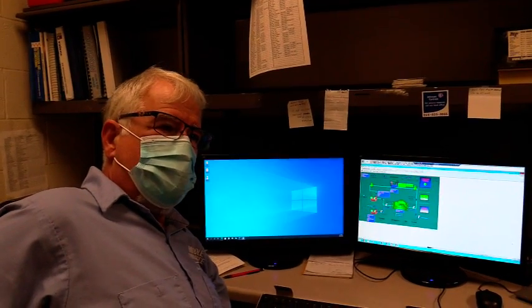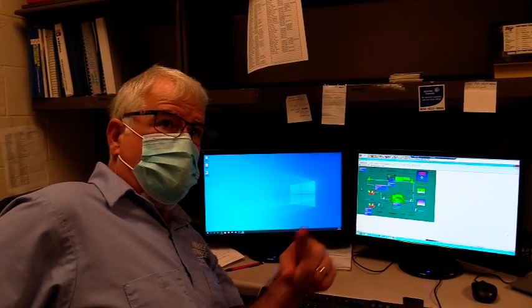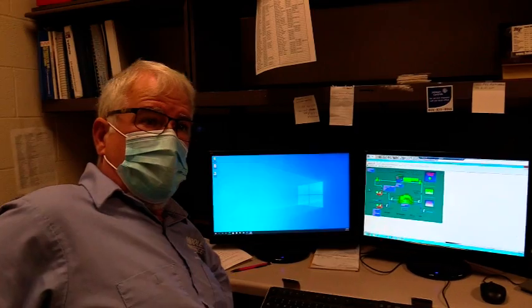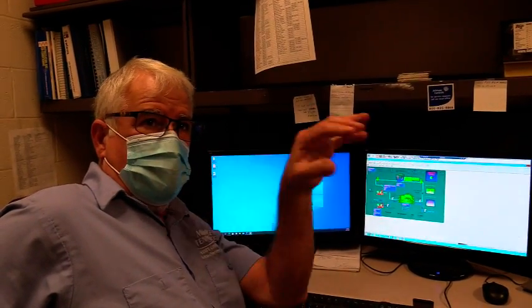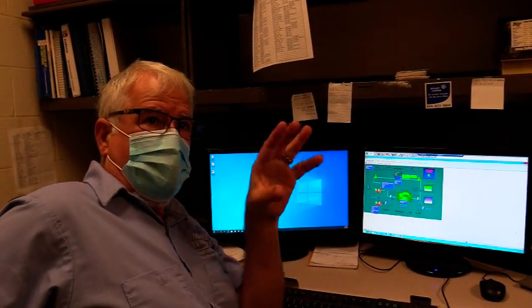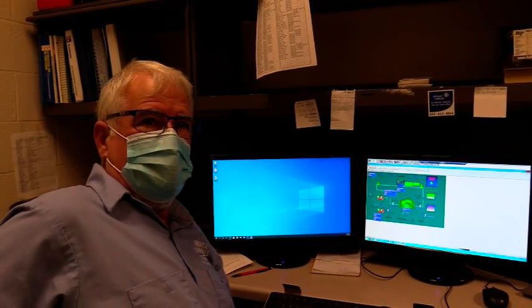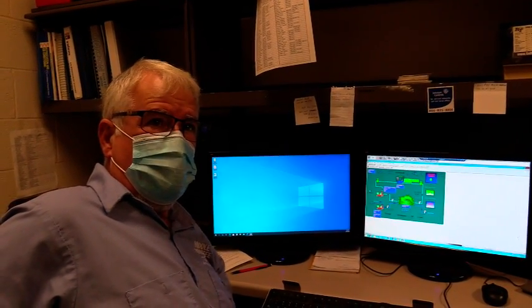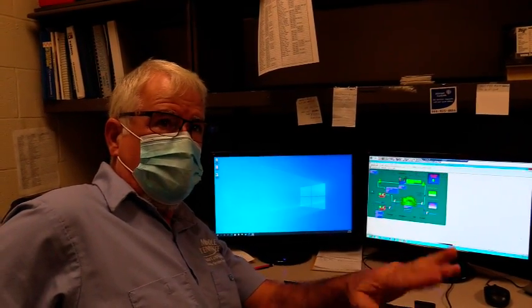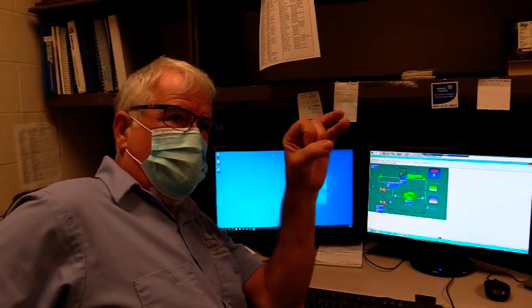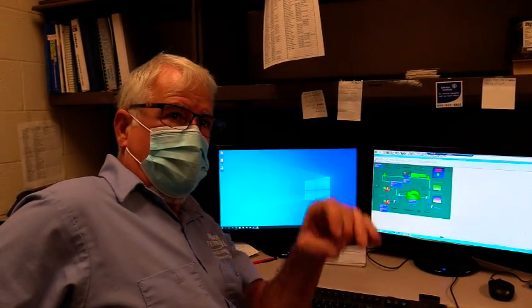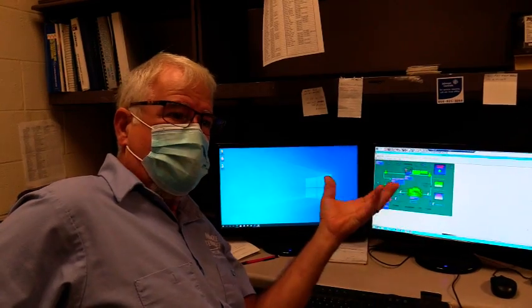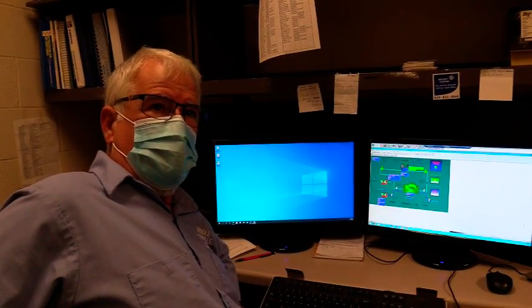Well, if I'm going to shut one off and change chillers, I start up the one I'm going to start first before I turn off the other one. That way, it gives you time to see how long it takes to start up. My water will get a little bit warm if I did that, so I just give it a head start, and you don't notice it until it gets between 20 and 30%. So when it gets about 30%, I'll turn off the other chiller.